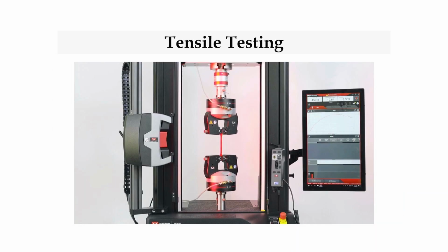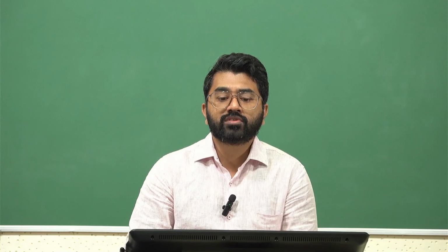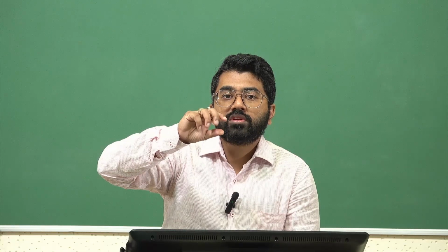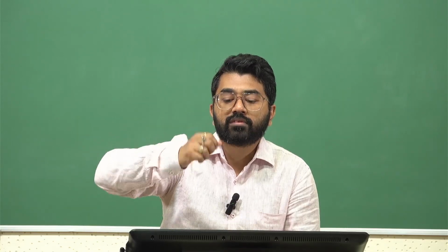Okay, further into the tensile testing system, this is how a much more professional tensile testing system looks. This is from Instron. It's a very popular manufacturer which makes some of the high precision universal tensile testing machines. Here you're looking at very sophisticated grips, or clamps, on the top and bottom, which are specifically made for soft tissue clamping, and have very high precision clamping techniques, just to make sure the tissue is not overstressed, understressed, and it doesn't break, right?